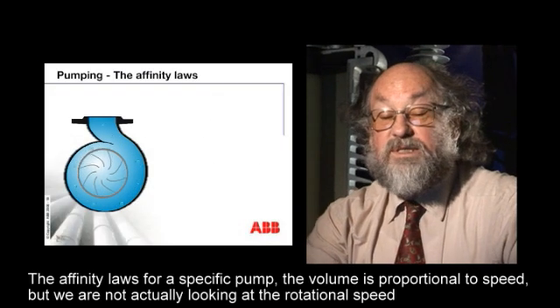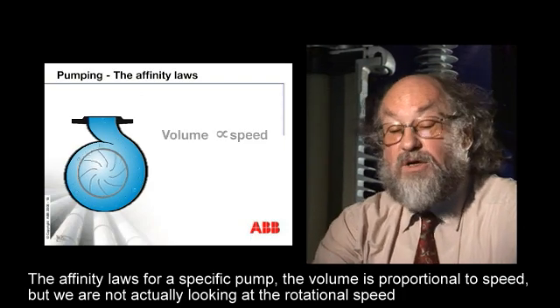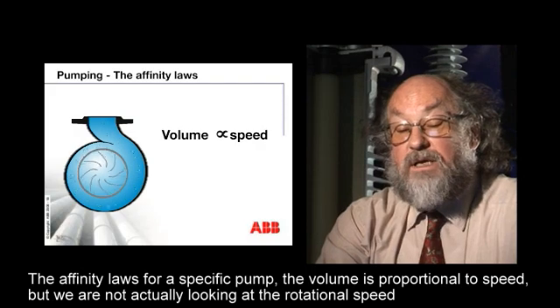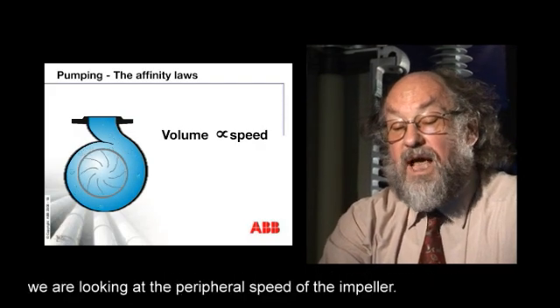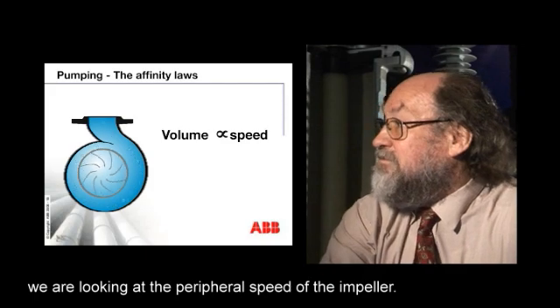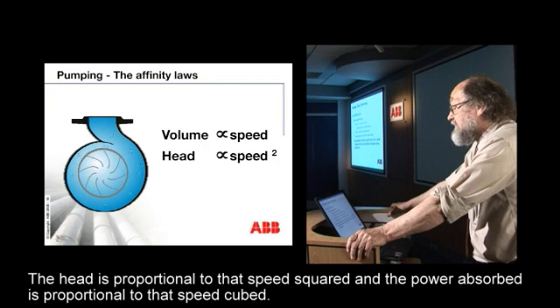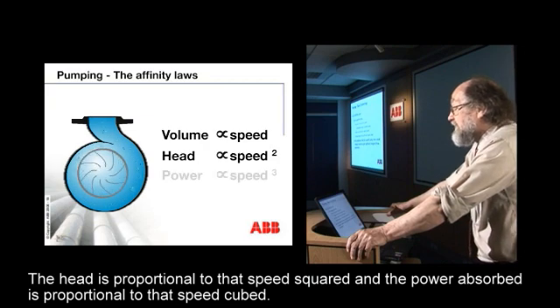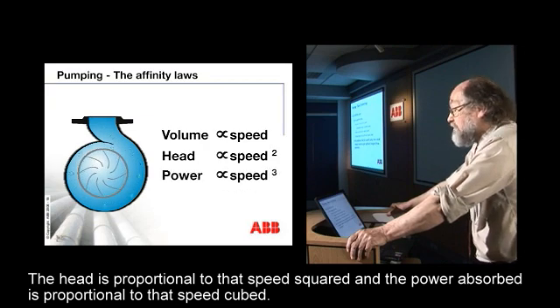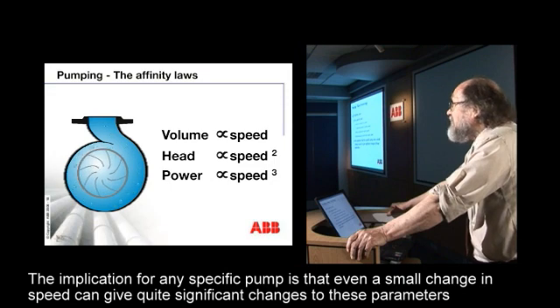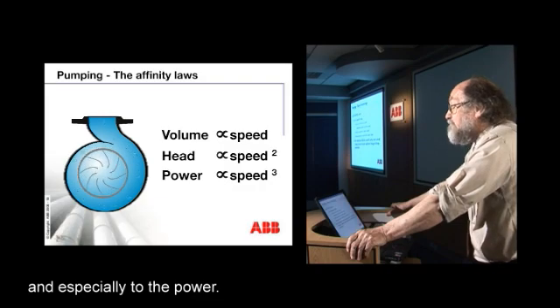The affinity laws for a specific pump state that volume is proportional to speed — specifically the peripheral speed of the impeller. The head is proportional to that speed squared, and the power absorbed is proportional to that speed cubed. The implication is that even a small change in speed can give quite significant changes to these parameters, and especially to the power.